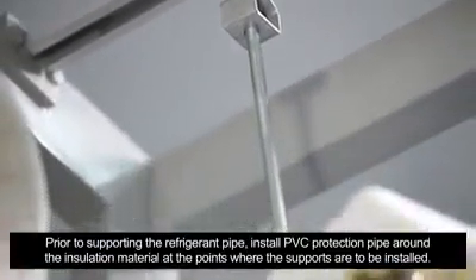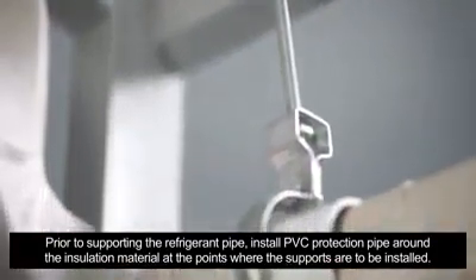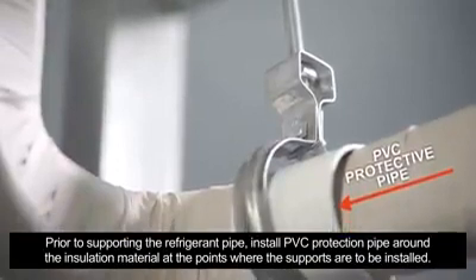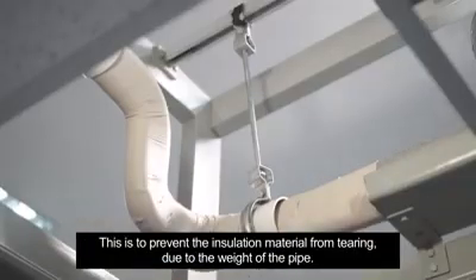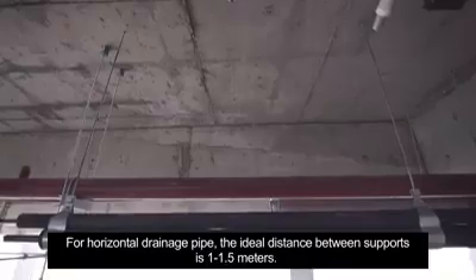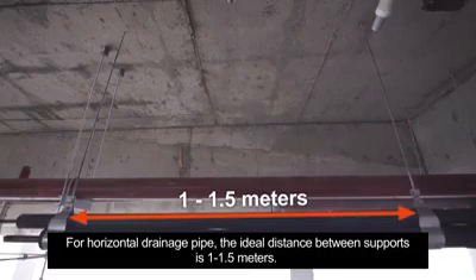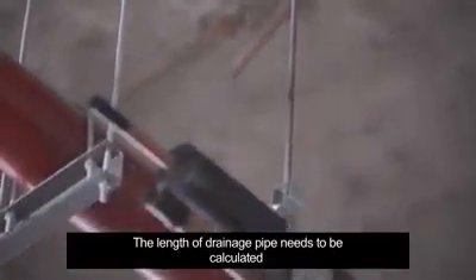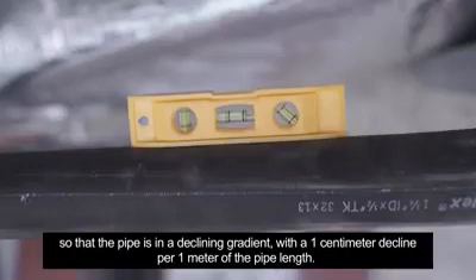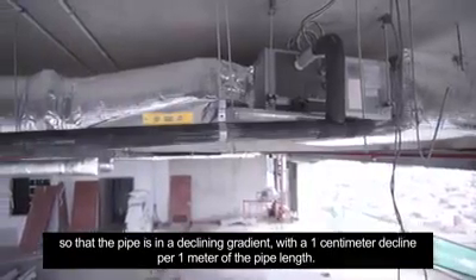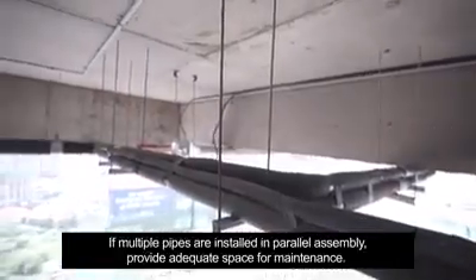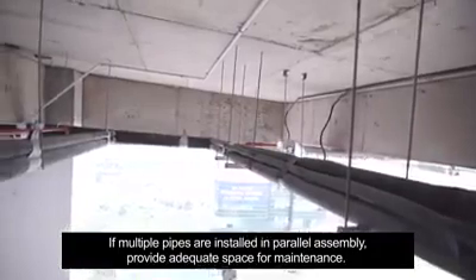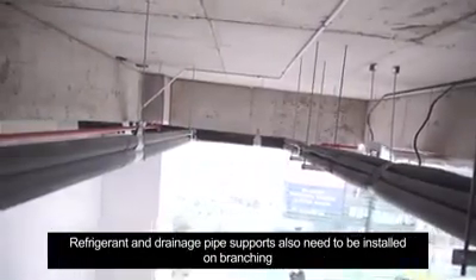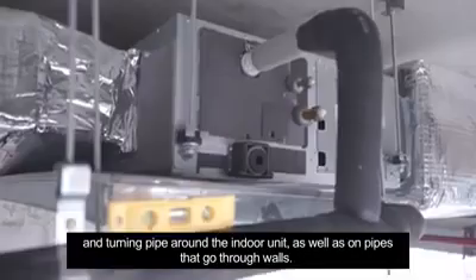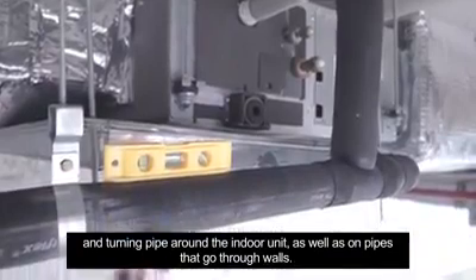Prior to supporting the refrigerant pipe, install PVC protective pipe around the insulation material at the points where the supports are to be installed. This is to prevent the insulation material from tearing due to the weight of the pipe. For horizontal drainage pipe, the ideal distance between supports is 1 to 1.5 meters. The length of drainage pipe needs to be calculated so that the pipe is in a declining gradient, with a 1 centimeter decline per 1 meter of the pipe length. If multiple pipes are installed in parallel assembly, provide adequate space for maintenance. Refrigerant and drainage pipe supports also need to be installed on branching and turning pipe around the indoor unit, as well as on pipes that go through walls.